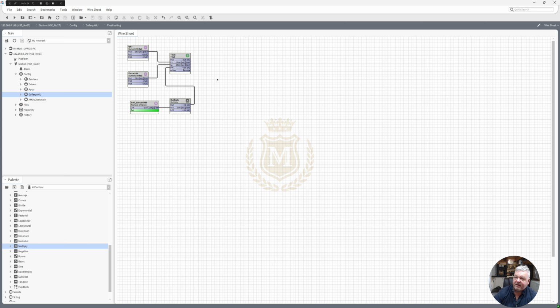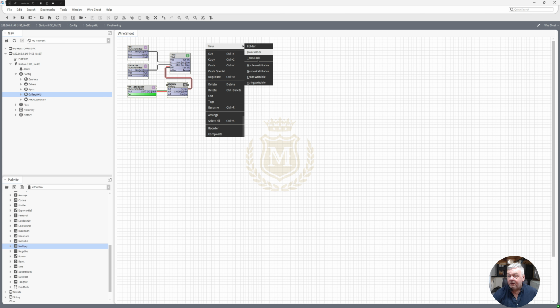So that's us taking the outside air temperature and making sure that it's lower than the extract air temperature of whatever we set there, in this case 2 degrees. And that gives us our output ready to do the cooling. That is your free cooling.